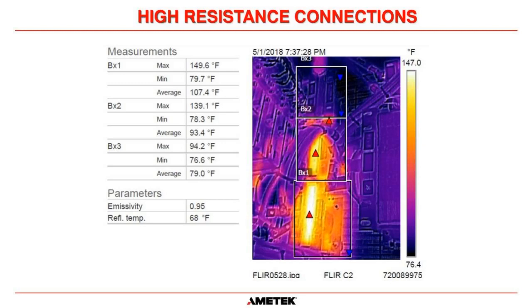And in this circumstance here, when we went to check it out after we had started it up, in these three boxes here, we have a choke or an inductor in each box, okay? And as you can see, the bottom inductor is hot, the middle inductor is hot, but the top inductor is not. And this is actually kind of the opposite of what I just spoke about in the previous slide. All of these inductors should be relatively warm because they dissipate heat when they are in operation. Transformers and coils, due to their inherent nature, they do dissipate quite a lot of heat. So that top choke should have been the same temperature as the bottom two chokes.